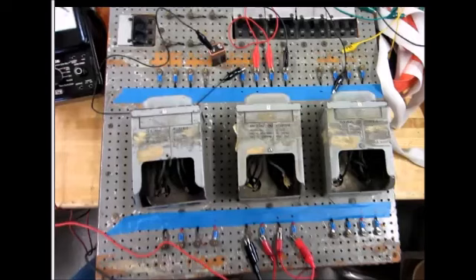Hi, this is Minhee again, showing the kick test on a board. This is my DC battery, connected to the positive polarity. These are two jumpers connecting the winding - the primary has one jumper and the secondary has one jumper, connecting the polarities and putting the coils in series. Both primary and secondary have that.